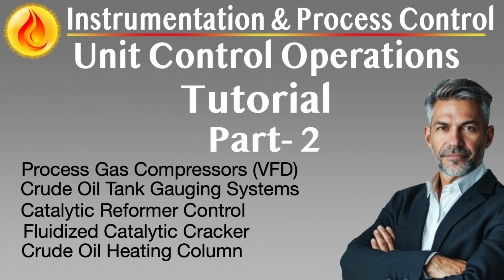Modern FCC control systems integrate advanced instrumentation, predictive models, and plant-wide optimization logic, making FCC units key beneficiaries of digital transformation and autonomous control technologies. At the heart of FCC control is conversion severity management, primarily governed by reactor temperature, catalyst activity, riser residence time, and feed preheat. Reactor temperature, typically in the range of 500 to 550 degrees Celsius, is controlled via the catalyst circulation rate, which is modulated by the spent catalyst standpipe and regenerated catalyst slide valve.